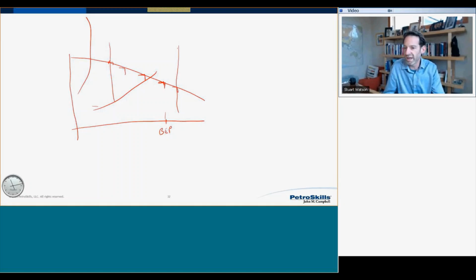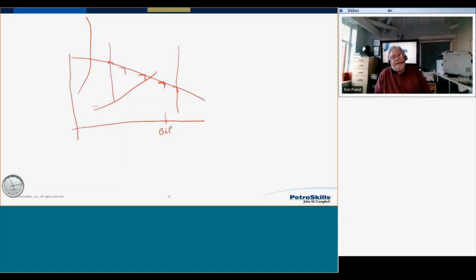One pump may deteriorate very quickly, another pump may not. So if you're trying from an operations perspective to understand what's happening, whenever we buy a pump, we should be asking for a pump performance test curve. Then we could take a couple of accurate pressure gauges or pressure transmitters and revalidate the performance of that pump back onto that pump curve, and evaluate how much erosion or wear has gone on. Yeah, I would say as well, Stu, the reliability guys should be doing this anyway. Your reliability guys should be looking at the pump curve and all of the parameters and saying, am I still on the pump curve? Because if I'm still on the pump curve, I don't need to strip the pump.